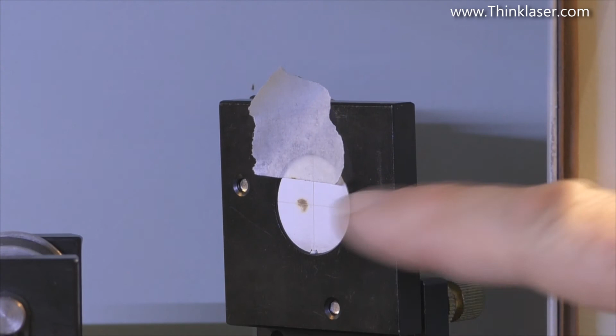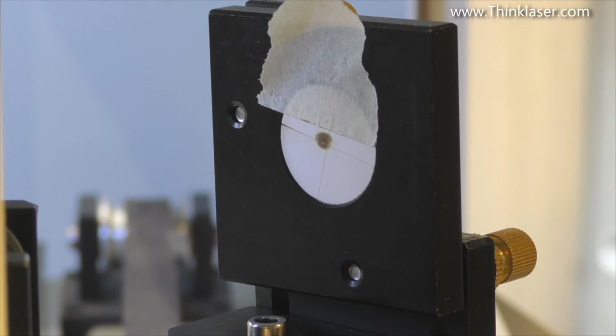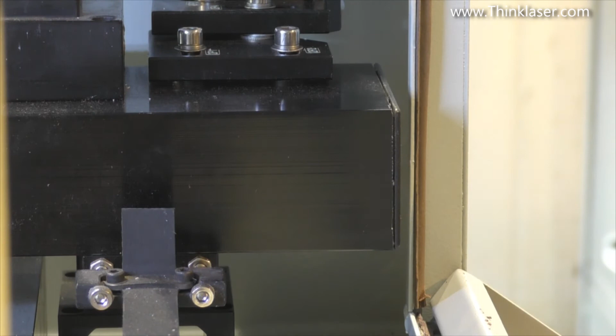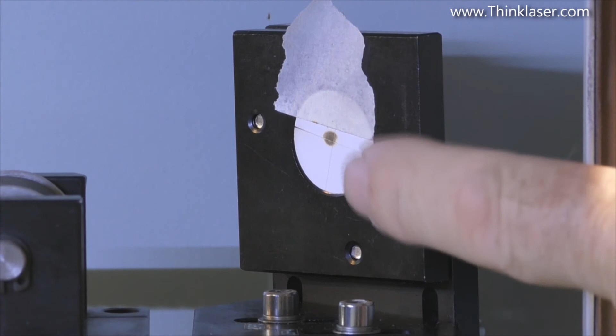We'll replace that target, and this time we'll bring the head right to the back of the machine. This burn is what I call a target burn. Okay, now that's our marker. It's actually not bad. Move back to the front of the machine. And now what we've got to do is make a mark that matches that one. We've got to adjust the mirror so that the two marks are coincident. As you can see, it's very slightly to the right. So I need to take a little bit off that mirror. Too much.